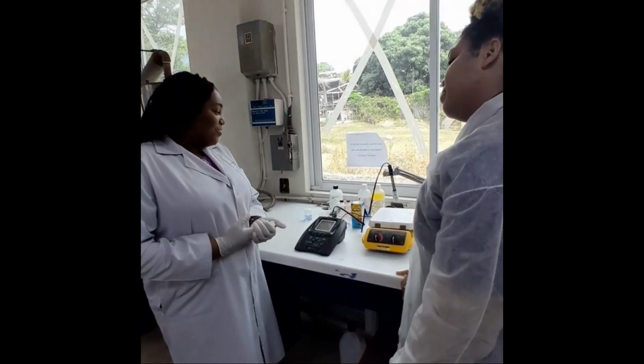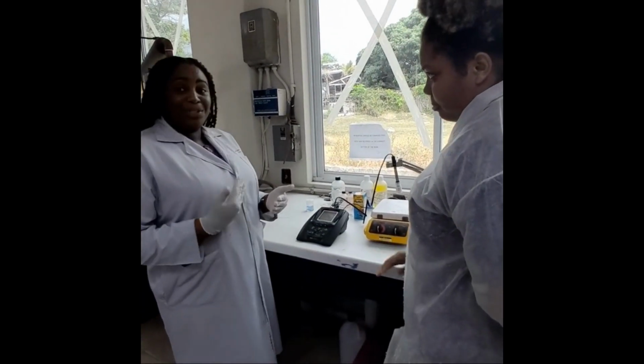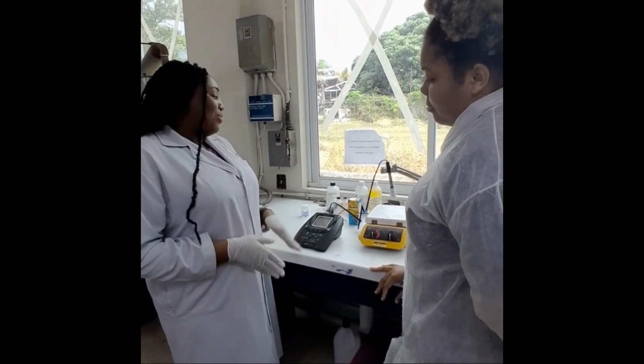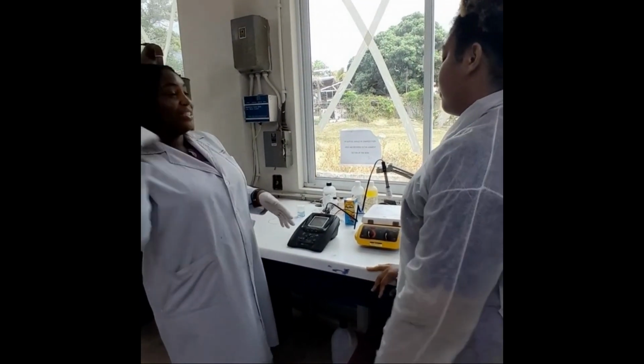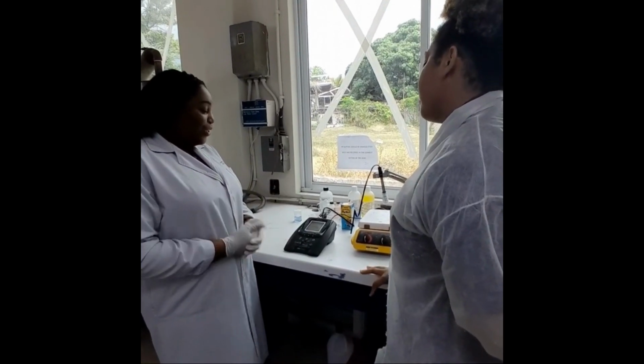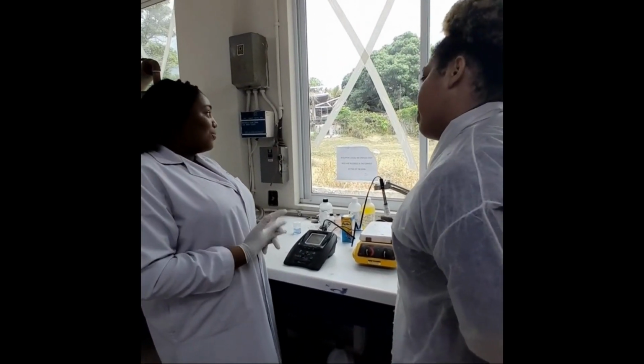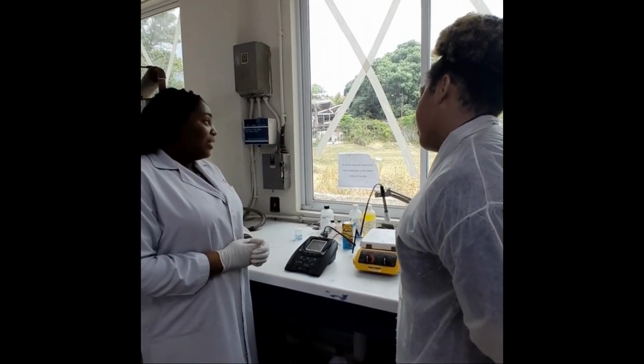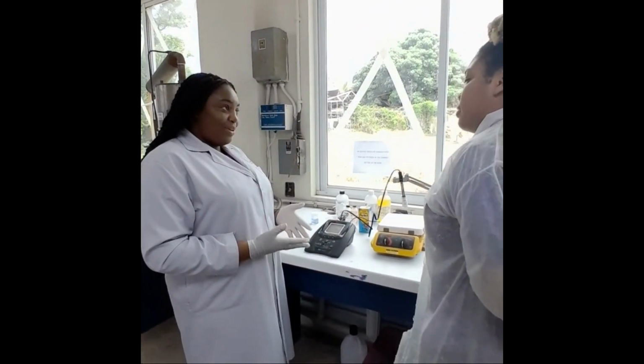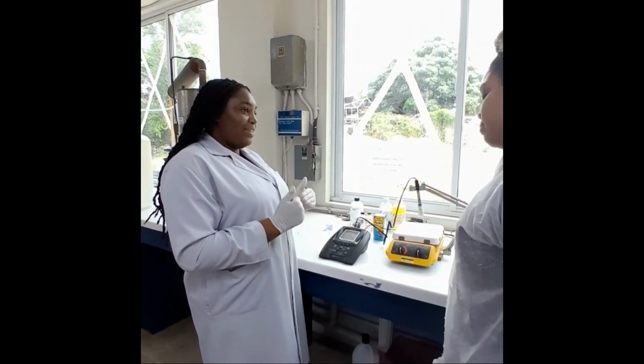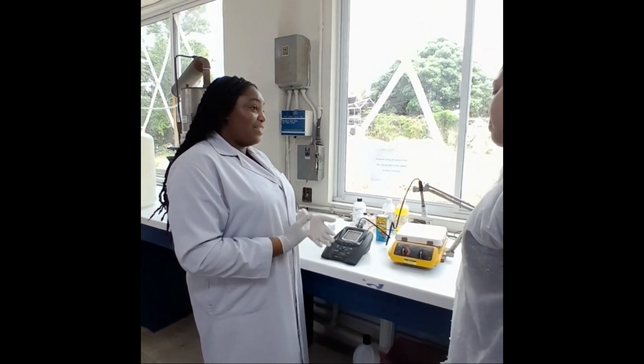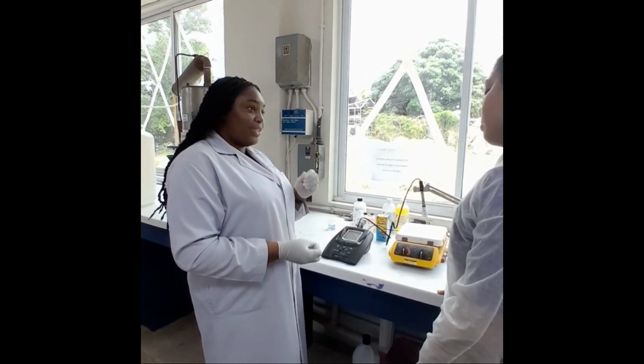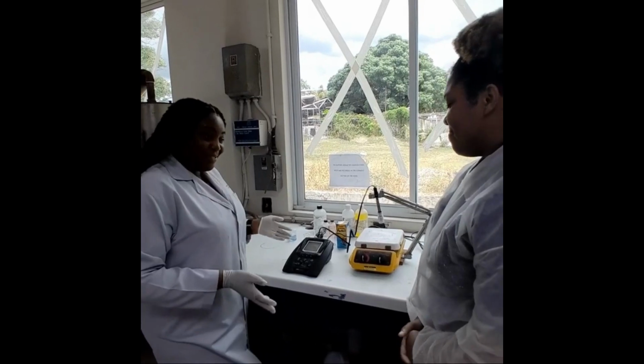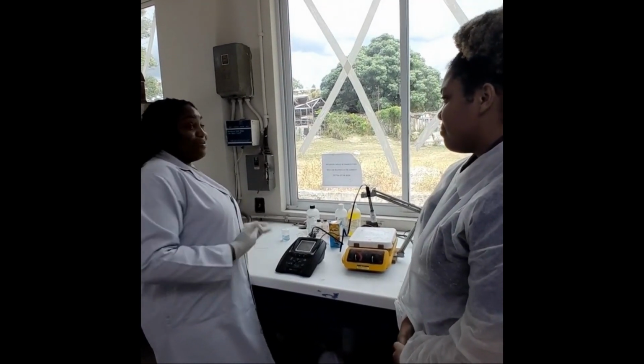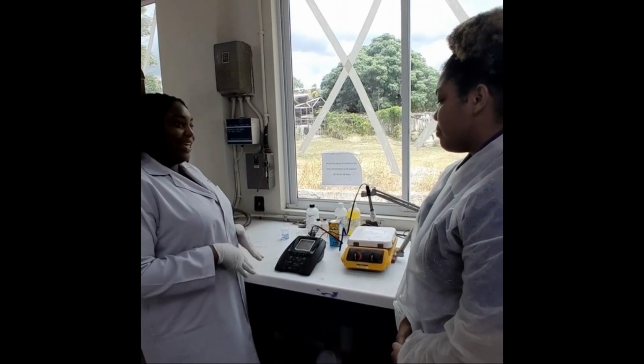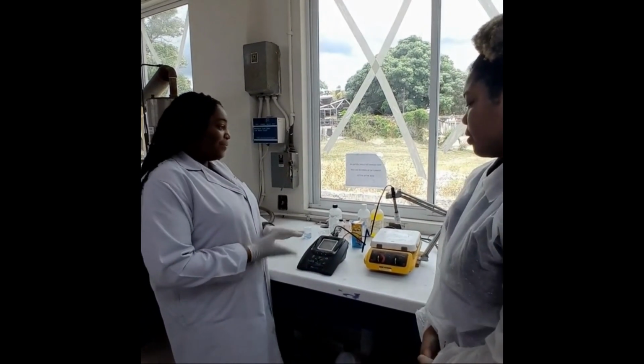Alright, that is a good reasoning, and that's good too, you need to check because somebody might have calibrated it using different solutions, and what you're measuring has a different pH, so you will have to recalibrate. But initially, what I was looking for, you need to calibrate a pH meter because you need a reference. So when you calibrate it, you have a reference to say between this and this is what the pH is, and you can see where your sample falls within that calibration range. If I'm going too fast, or if there's something you don't understand, just stop me and I'll explain to you so you can get it.